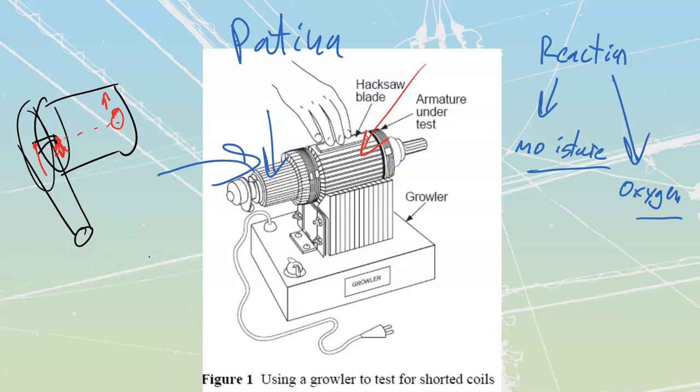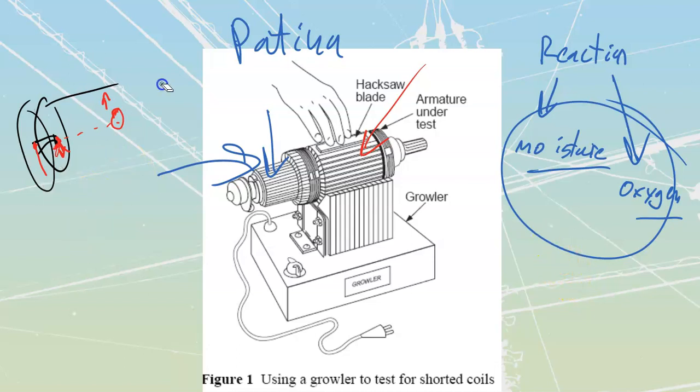It's going to just be that brownish color. I should not see bright copper through. Bright copper means that I've got too hard brushes. Where we start to lose these is when we place these things into areas that are operated under vacuum. You must be very careful when you are specking out motors.